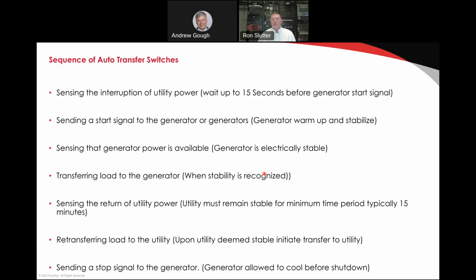Now, I can tell you this too. I've seen situations where the utility was back, but it was unstable. So although you looked at the front of the ATS and it said utility had returned, it did not consider it stable. It was still losing phases. The voltage was still messed up. And it took 24 hours, sometimes 2 days, for them to clean up the utility enough for it to be stable. And during that period of time, the ATS would not retransfer. That's okay. That's an environment in Florida where there are hurricanes and much damage going on. But once it's deemed to be stable, the load will return to utility.